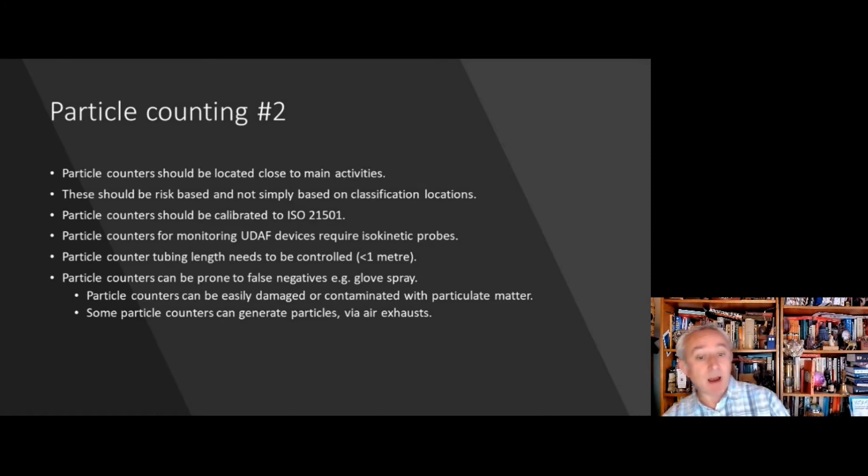For the data to be relevant, the particle counters should be located close to the main activities. The particle counters only have a certain range, so they need to be close to what we actually want to measure. To ensure better accuracy, these locations should be risk-based, not simply based upon locations used in classification, but informed with an awareness of what's actually going on in the area.